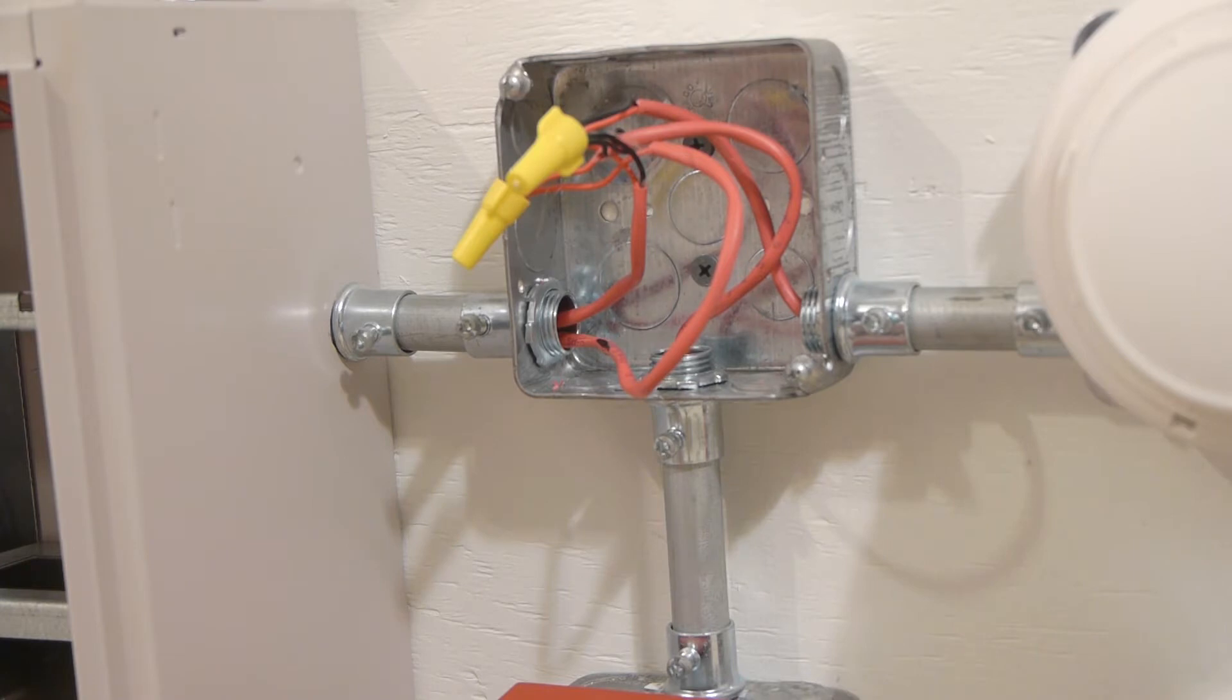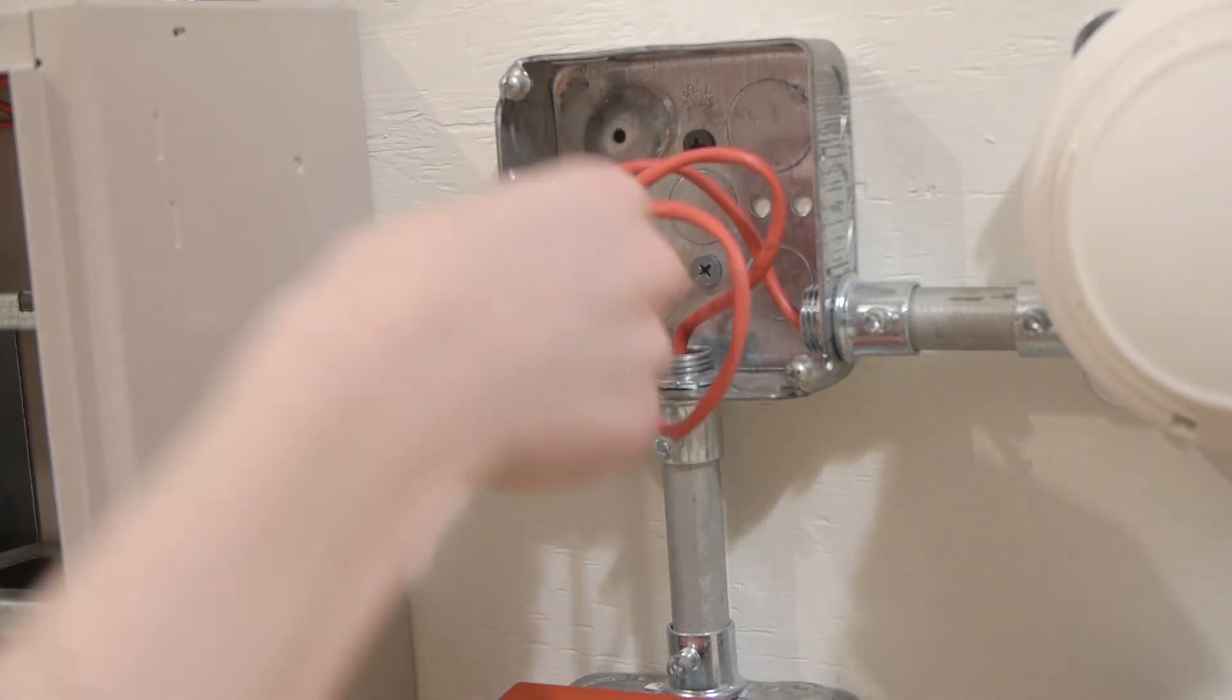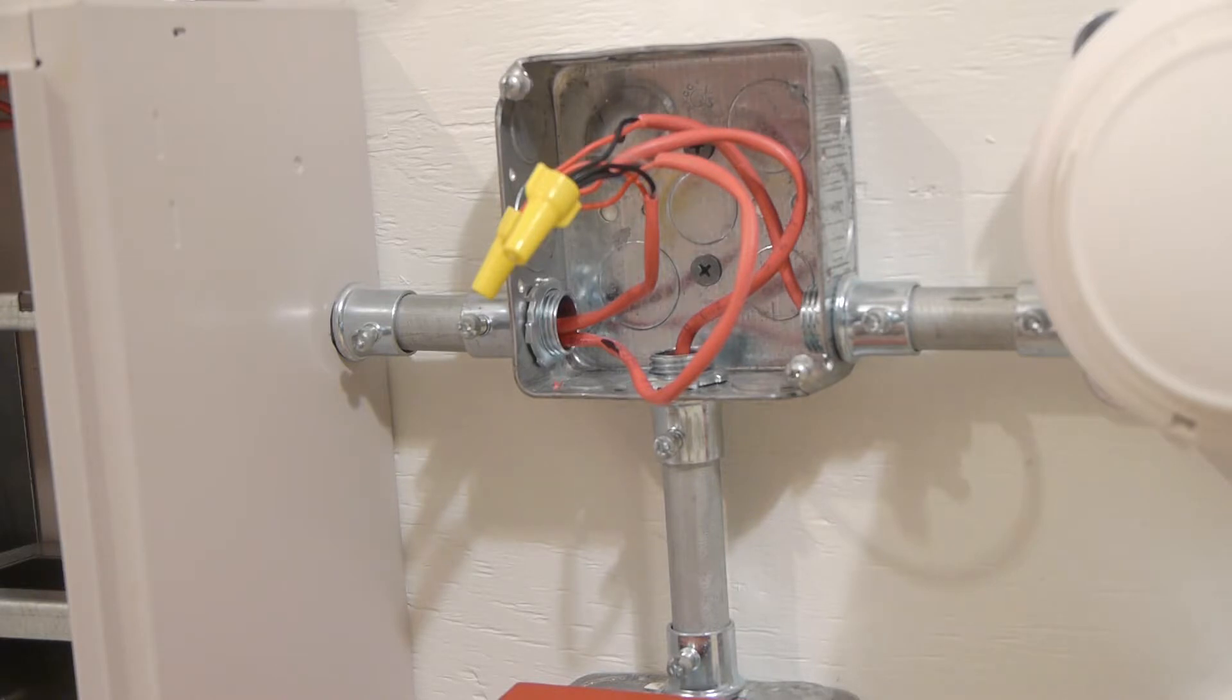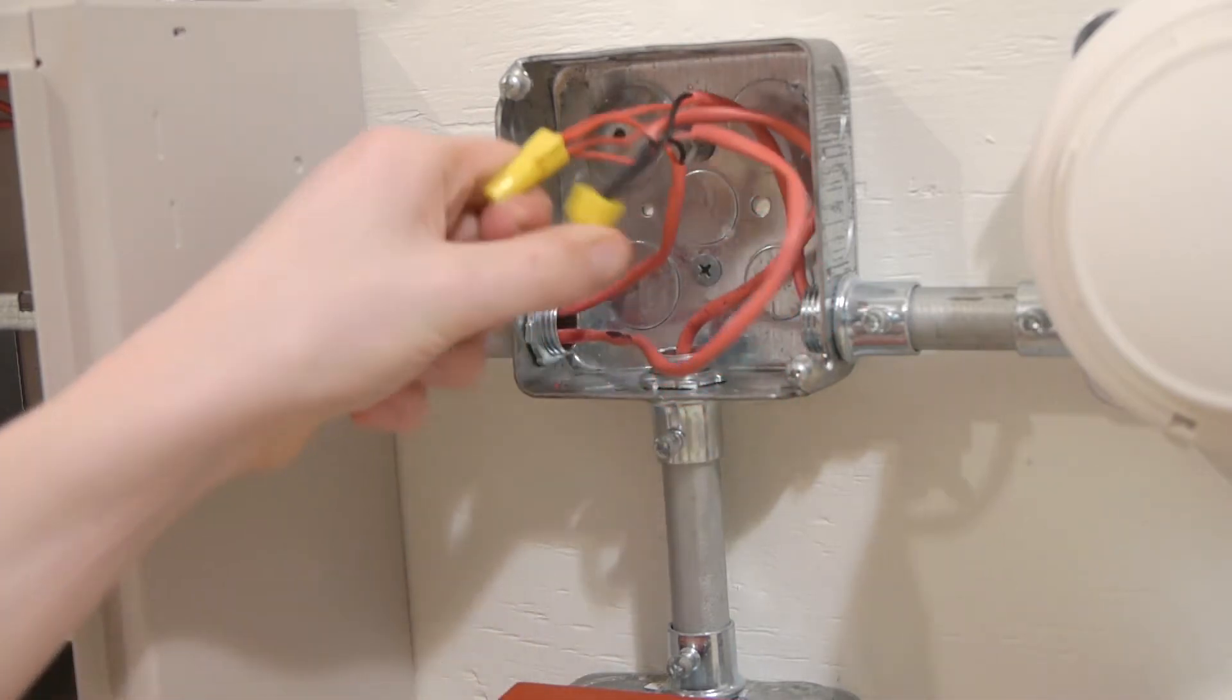Since we know it's a negative earth ground fault, we're going to pull apart the negative wire nut here. If you don't have a Simplex 4010 or your panel doesn't show if it's a negative or positive earth ground fault, just do the same thing I'm doing but with the positive and negative.